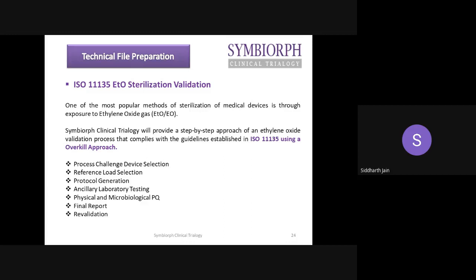So you have to validate your process with the help of the method called the overkill approach. You have to follow the ISO 11135 2014 version, and you have to carry out the process challenge device selection, reference load selection, protocol generation, and final report. There are different methods of doing it, and different steps of doing the validation.